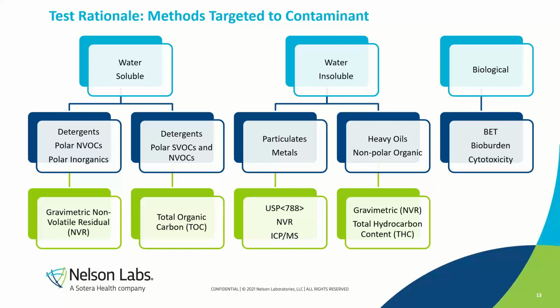So kind of backtracking a little bit to the particulates and the metals. This column can get a little complicated. So USP 788 is a particulate method. We would extract in water, and that extract would go on a light obscuration particle counter to give you a count of particles. Could be metal particles, could be fibers, could be polymer, it could be any number of things. And there is a microscope option instead of, or in addition to the light obscuration particle counter, which gives just a little more qualitative information.